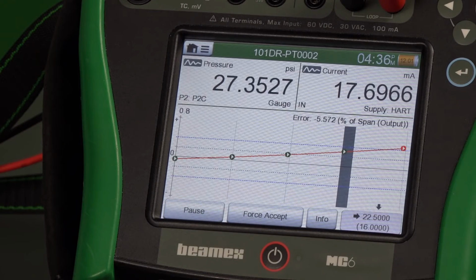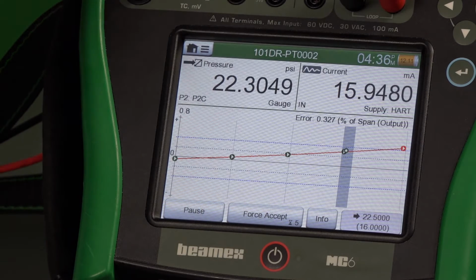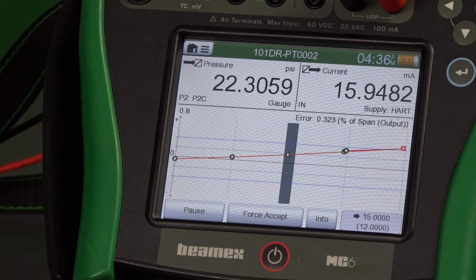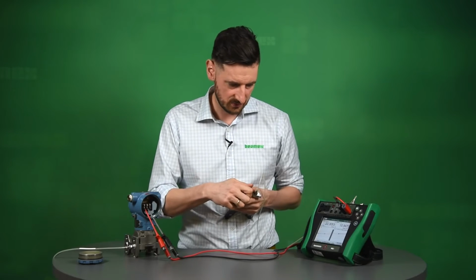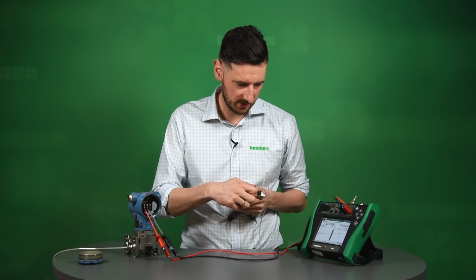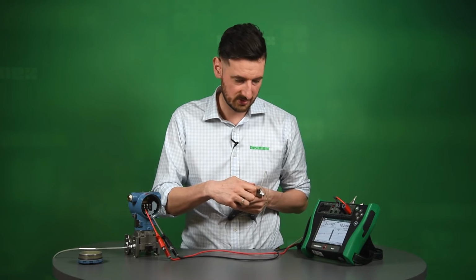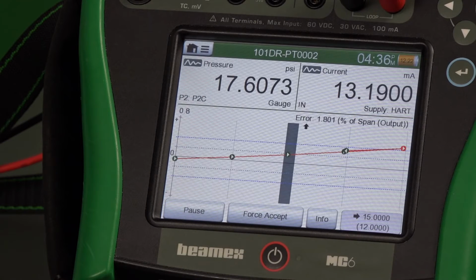Going down is probably more difficult than actually pumping, because you have to make sure that you don't go down too quickly, meaning you're not overshooting to that lower point. So if it's 22.5, just try to be there at 22.5. So be very careful when you actually open your pressure source. So trying to get there to 15, thereabout, and we are at 15 at 12 milliamps. So we wait there.